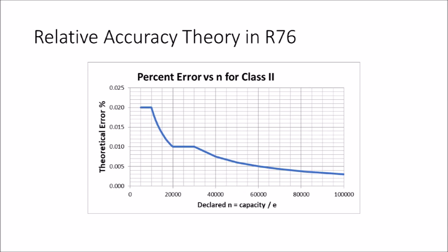But what's important is these really speak to the whole instrument. It's not 3 instruments at 100,000. In other words, 0 to 10,000 is one instrument, 10,000 to 30,000 is a second instrument, and 30,000 to 100,000 is a third instrument. No, it's one instrument, and essentially the manufacturer is trying to make sure that the D of their instrument is accurate within the percent accuracy you see in this table based on the N for the instrument.